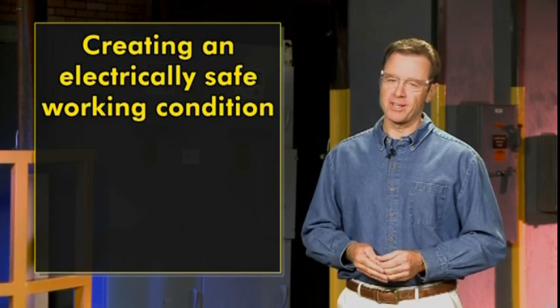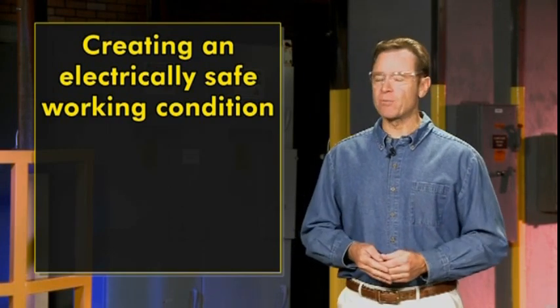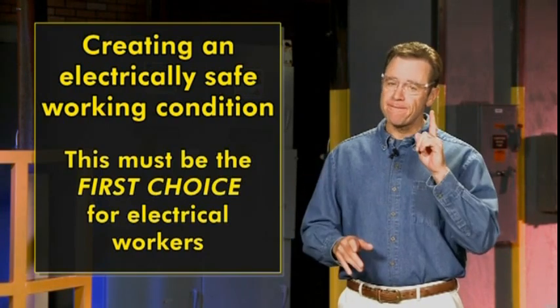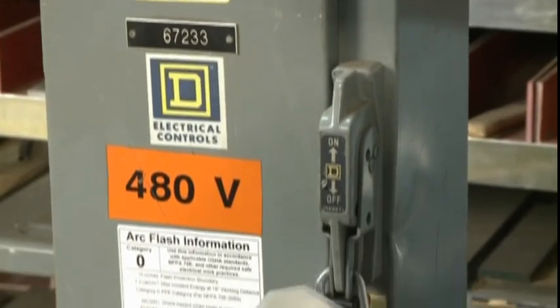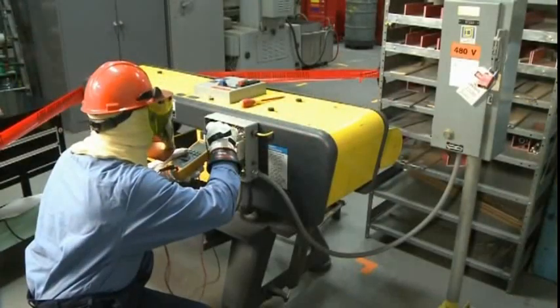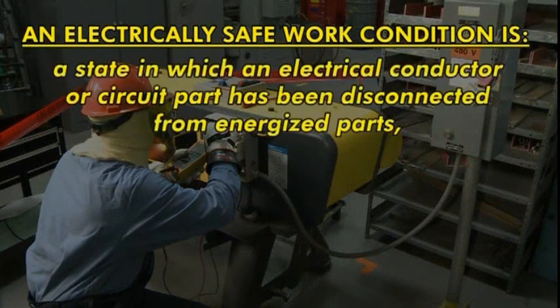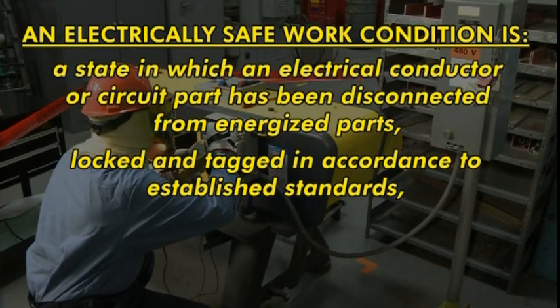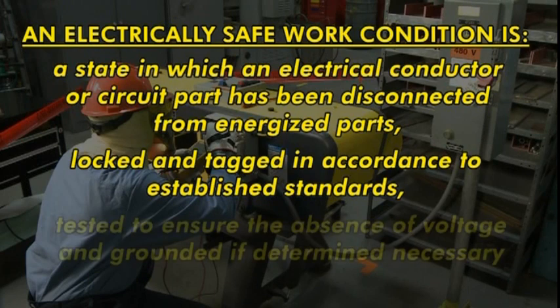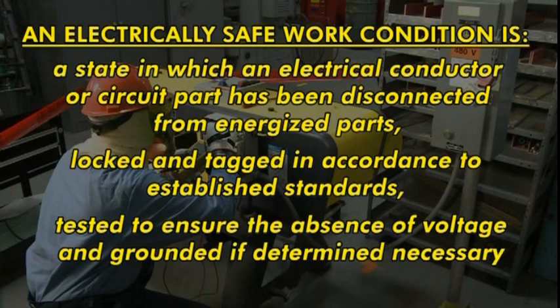Let's next discuss the most effective way to prevent any type of injury related to electrical hazards: creating an electrically safe working condition. Creating an electrically safe working condition must always be the first choice for electrical workers. The NFPA's definition of an electrically safe work condition is a state in which an electrical conductor or circuit part has been disconnected from energized parts, locked and tagged in accordance to established standards, tested to ensure the absence of voltage, and grounded if determined necessary.